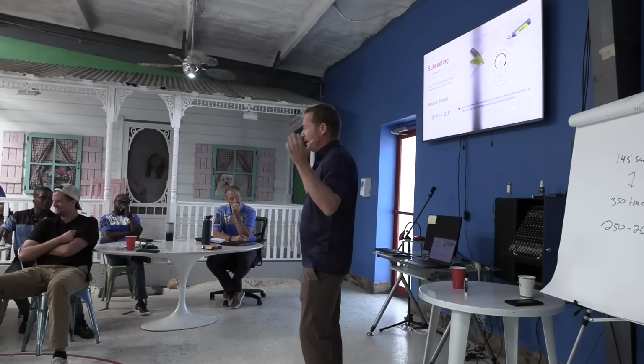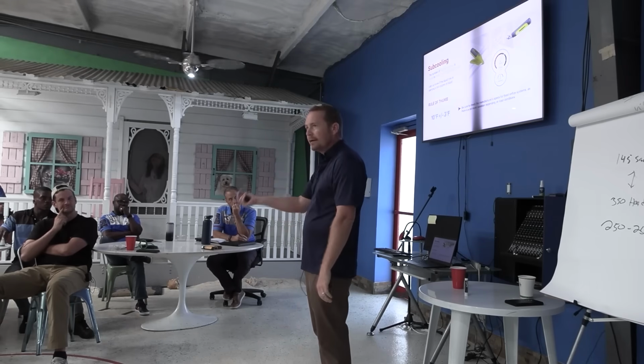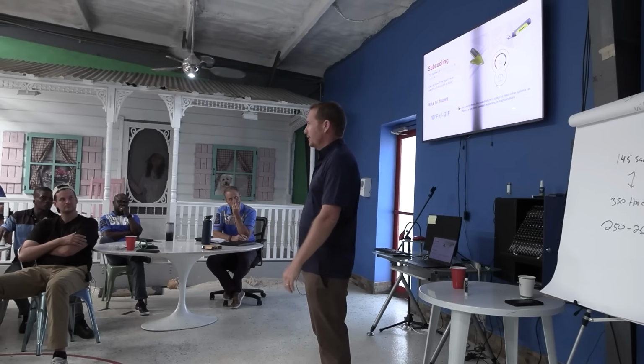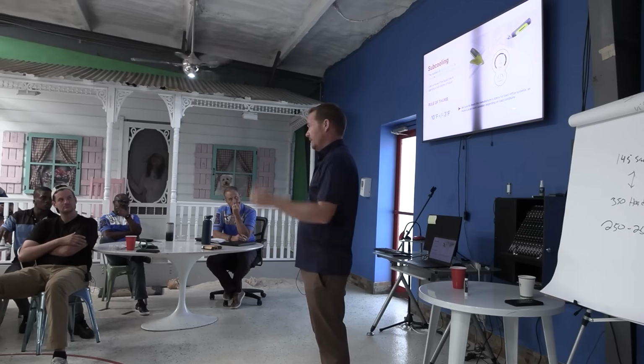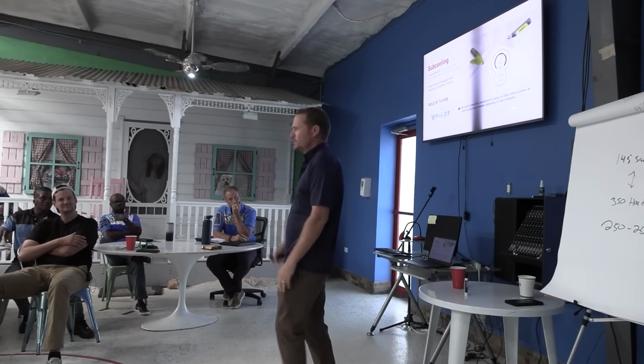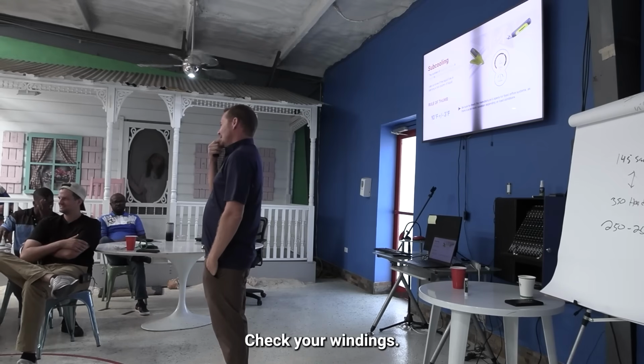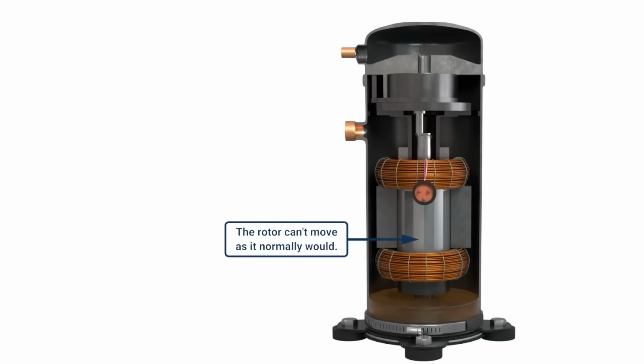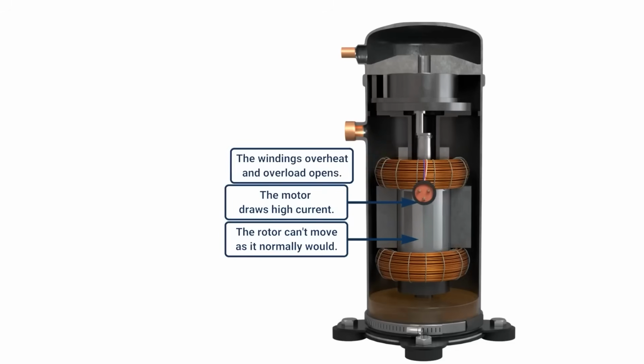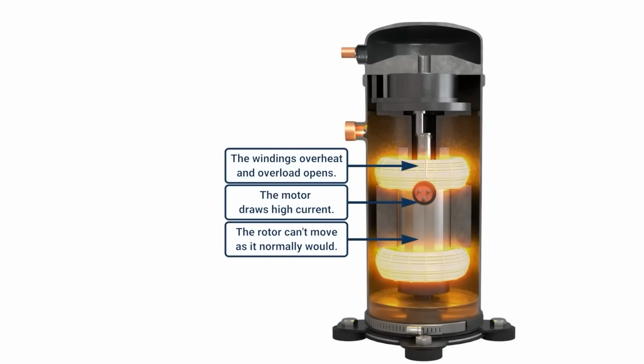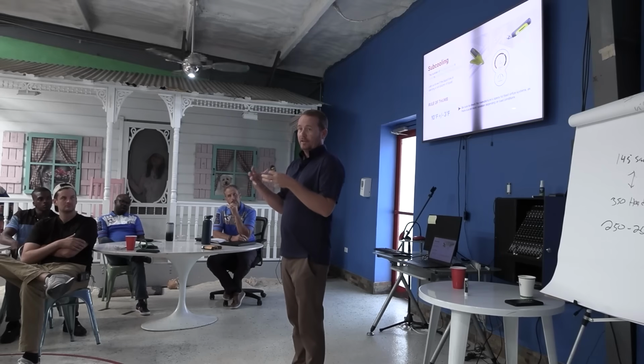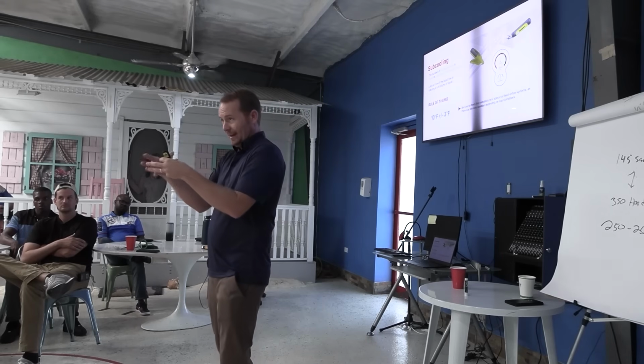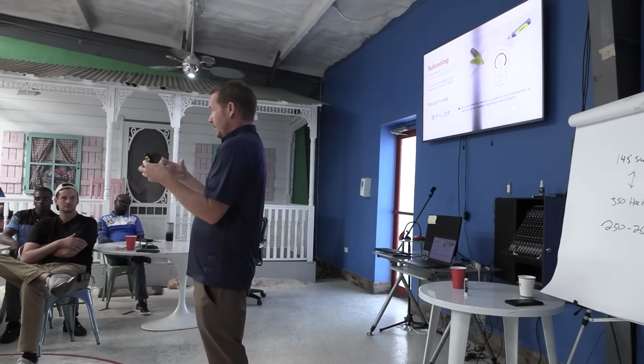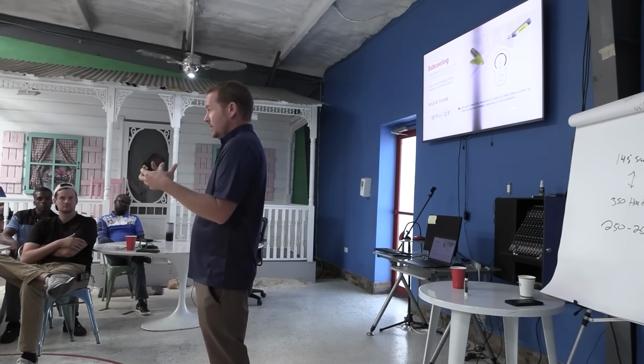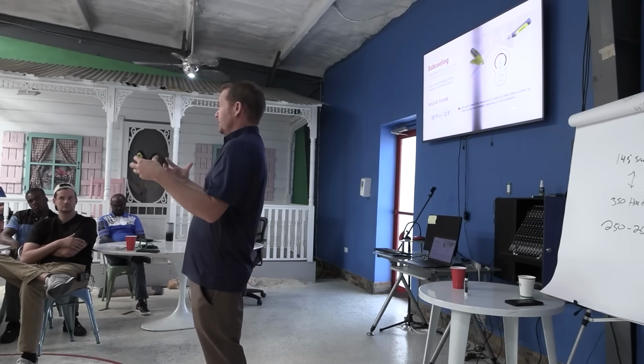Why, when it's a bad capacitor, does it just reset so quick? It just keeps doing it. When it's high head pressure, the thing is hotter than a hot thing. Hotter than a polar bear. I don't know. It's really hot. Because that thermal limit is located in the windings. When the compressor's locked, which is what happens when the capacitor's failed, it can't spin, right? Those windings just become little heaters. But all of that heat is contained in the windings, the actual electrical windings, and that's what's tripping that limit, and that limit is right there with the windings. So it heats up real quick, cools down real quick, heats up real quick, cools down real quick.